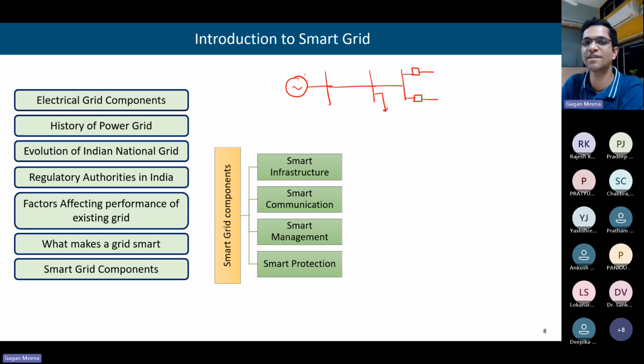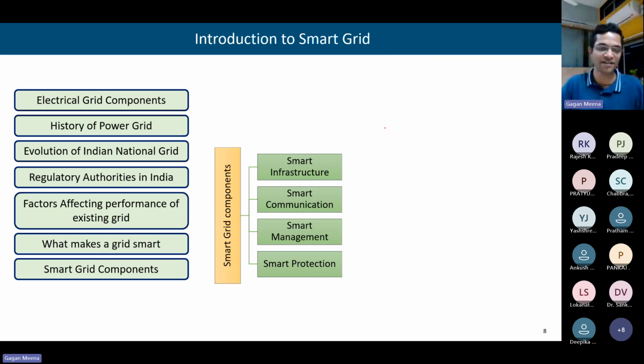If the system is connected to the grid, the fault current is different. If it is isolated and working as a microgrid with different DERs and storage devices, the fault current is different again. For both scenarios, and for different penetration of RE or different modes of inverter operation, the protection scheme should be agnostic of these changes. For that, we need adaptive protection schemes, which is why we call it smart protection: it detects changes in the system, adapts itself, still protects the system, and reconfigures when the system is reconnected to the grid.